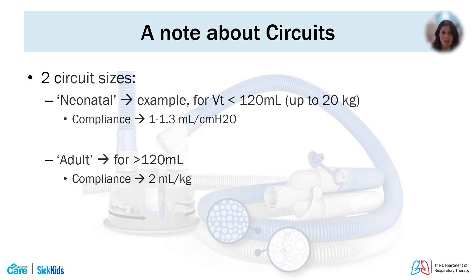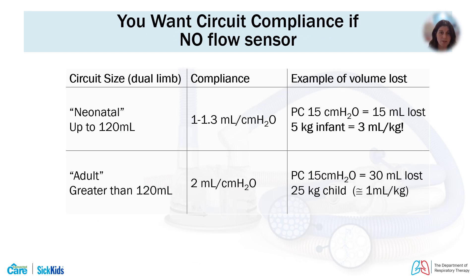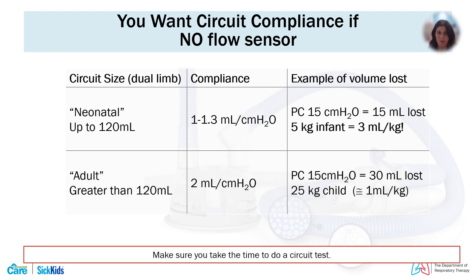Circuit compliance becomes really important. You will want circuit compliance compensation on for tidal volume measurement if you are not using a flow sensor. For example, a 5-kilogram infant on pressure control of 15 with a circuit compliance of 1 mL per centimeter of water means approximately 15 mL is lost to the circuit, which will drastically impact your tidal volume assessment depending on whether compensation is on or off. This is less important if you are directly measuring volumes at the patient ETT using a flow sensor.